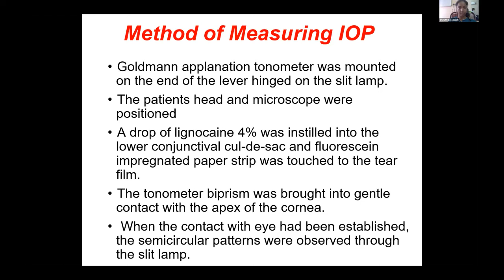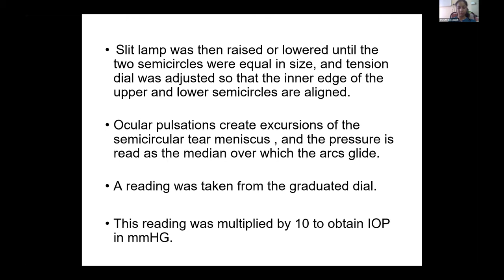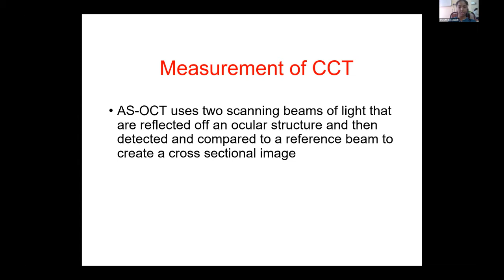Ocular pulsations create excursions of the semicircular tear meniscus, and the pressure is read as the median over which the arcs glide. A reading was taken from the graduated dial. This reading was multiplied by 10 to obtain IOP in mmHg. Measurement of CCT. Anterior segment OCT uses two scanning beams of light that are reflected off an ocular surface and then detected and compared to a reference beam to create a cross-sectional image.